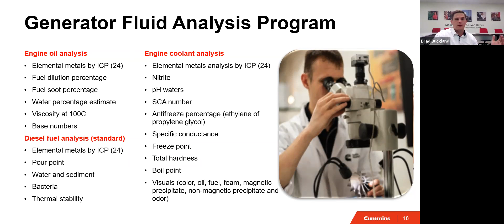These tests give you a health checkpoint as well, because if you keep your generator healthy, clean, and tested in planned maintenance, it can last a long time - I've seen generators in the field from the 80s still running. You keep it as good as you can, and eventually the technology catches up with more efficient controllers and upgrades. So your generator most likely won't be the one failing on you - the technology just ends up surpassing it, but it won't break down. It's like comparing an iPhone 12 or 15 to an iPhone 4. That's why we test these things - to keep that generator going so you're not facing another costly expense of buying a brand new generator.